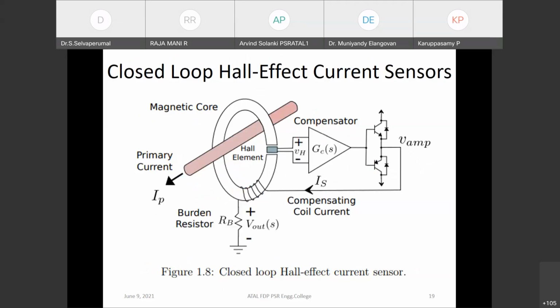In open loop current sensors, when the current is large, the core flux becomes high and may saturate. So the operating point may deviate from the linear range of the BH curve, resulting in non-linear Vh, right? Also, the saturation flux density of the core puts a restriction on the upper limit of the measured current. So for example, if the core is nickel iron alloy with a saturation flux density of 600 millitesla at 25 degrees centigrade and an air gap length of 0.5 millimeter, the maximum current that can be measured will be approximately 240 ampere, right? But the BH curve becomes highly non-linear near B saturation, right?